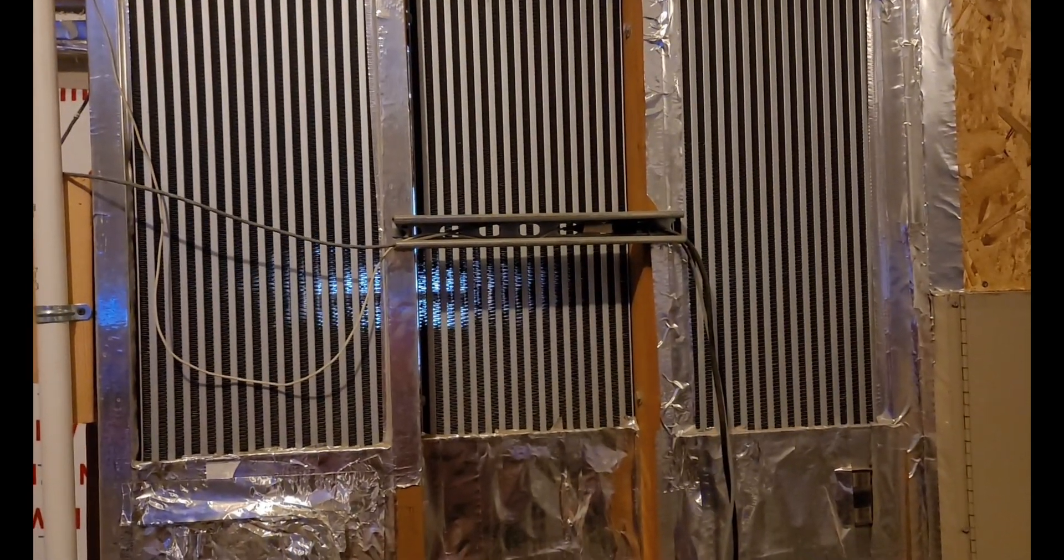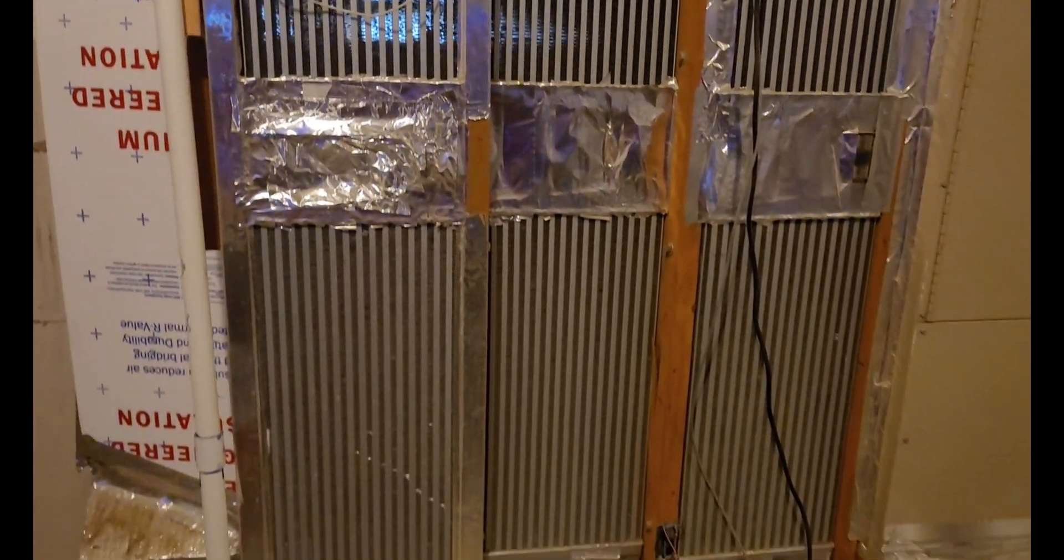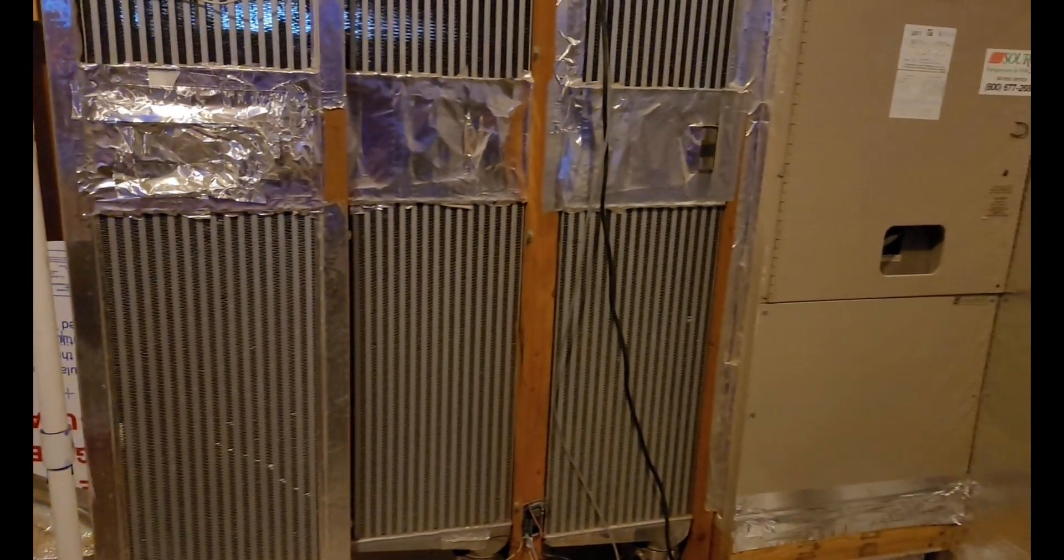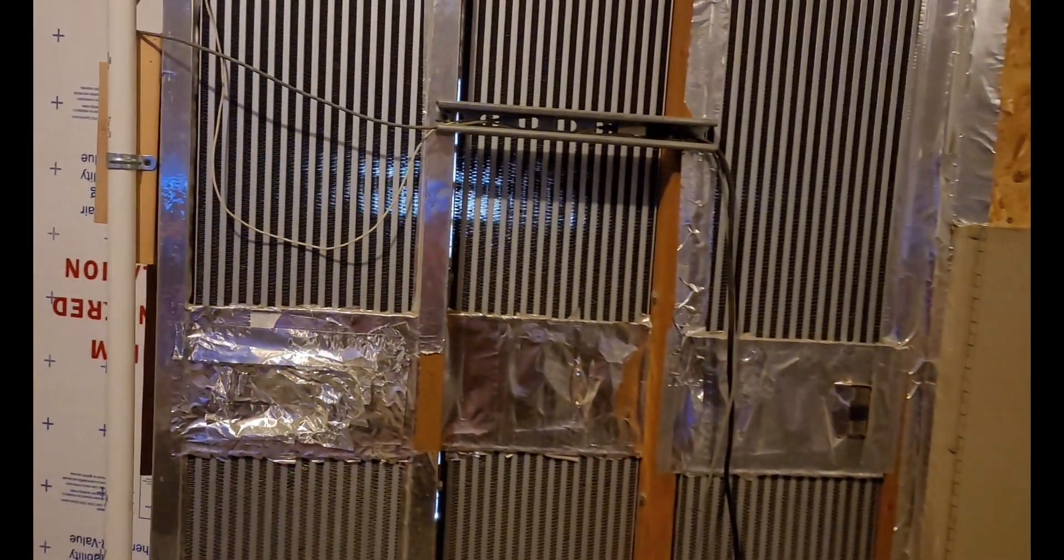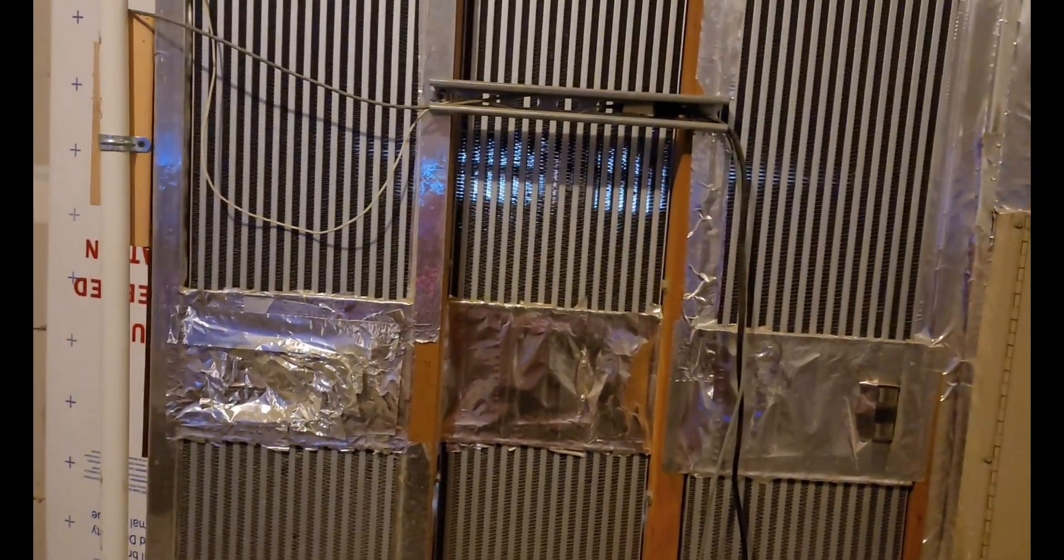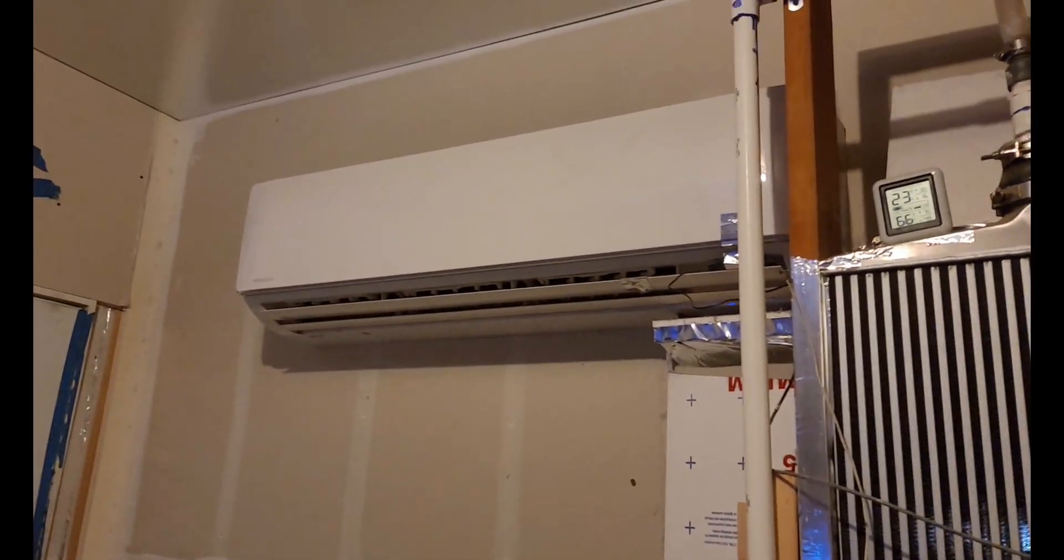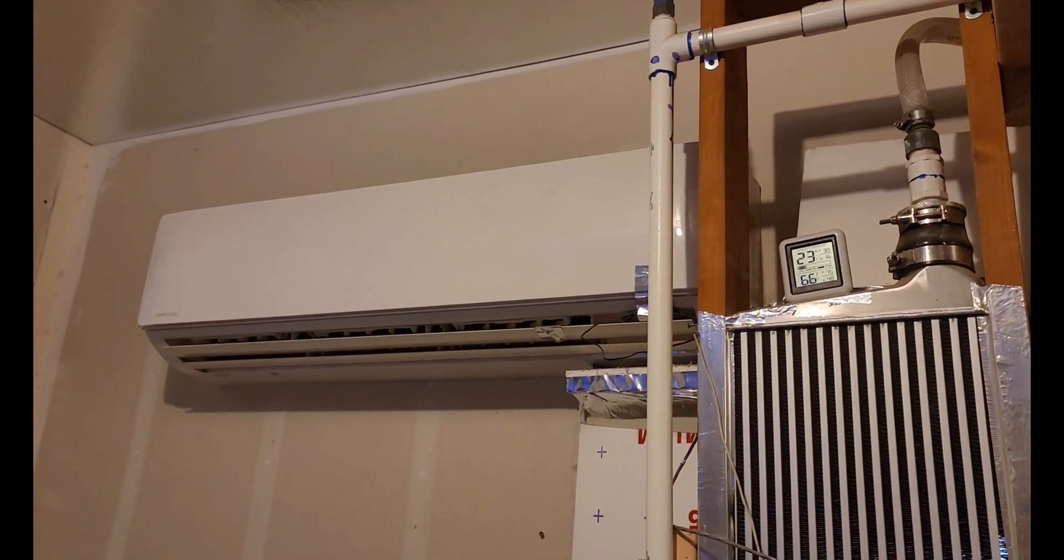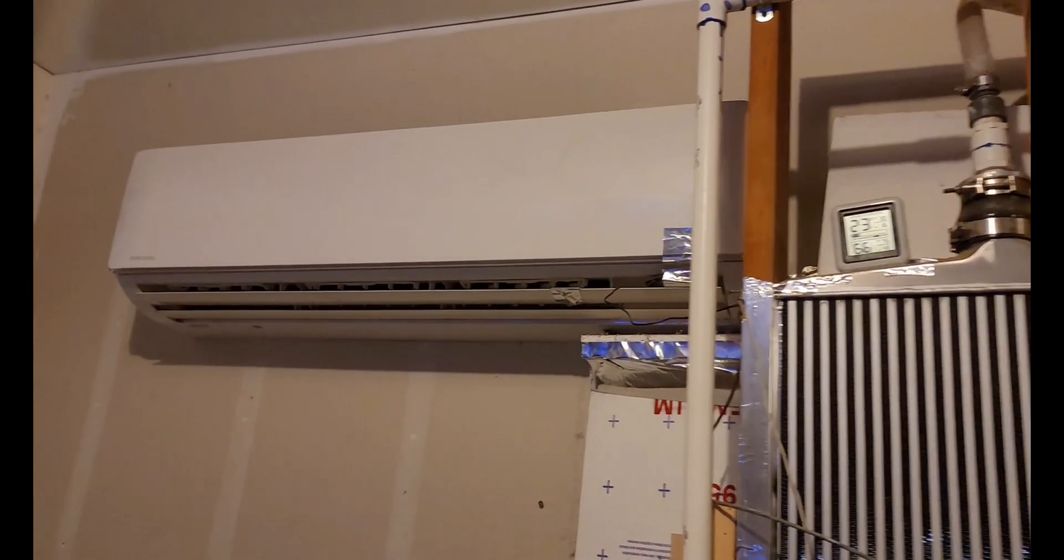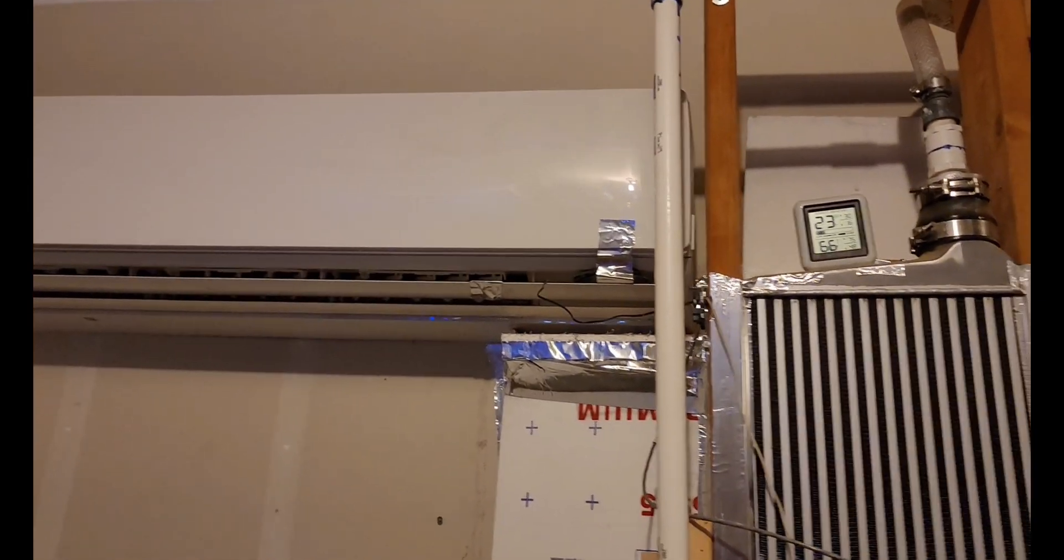The good thing about this AC is it is an inverter duty compressor, so because of that when it does fire up it actually ramps up slowly. It'd be like one amp, one and a quarter amp, two amps, three amps, little by little until it got to the point where it was full bore.